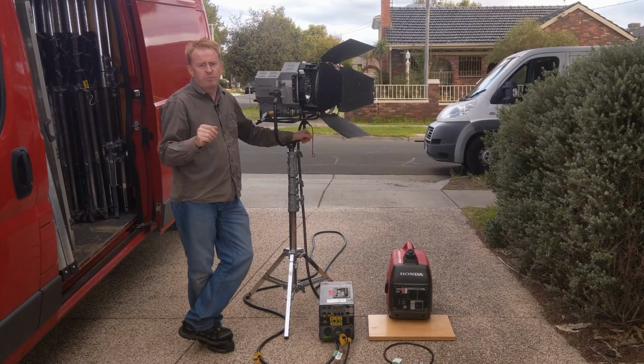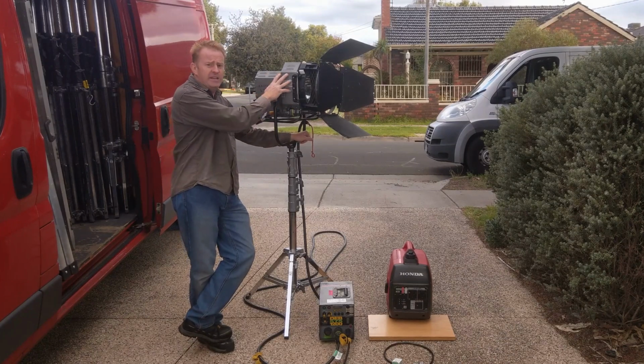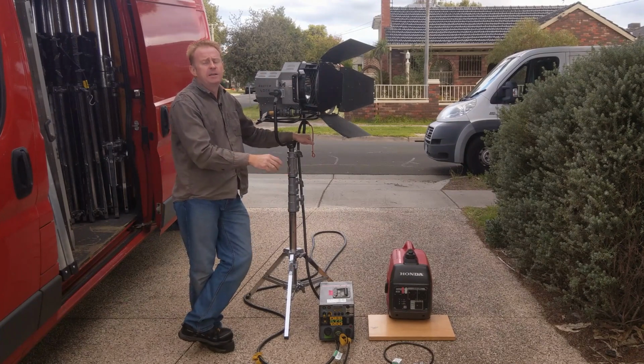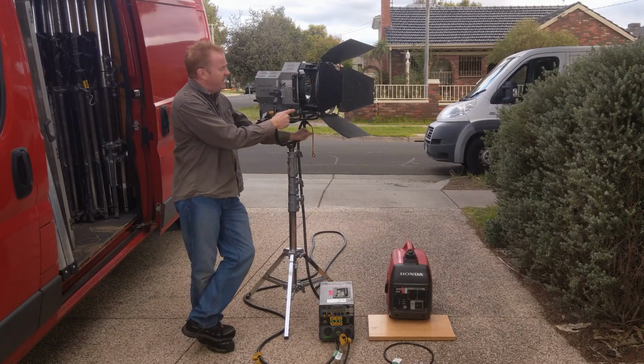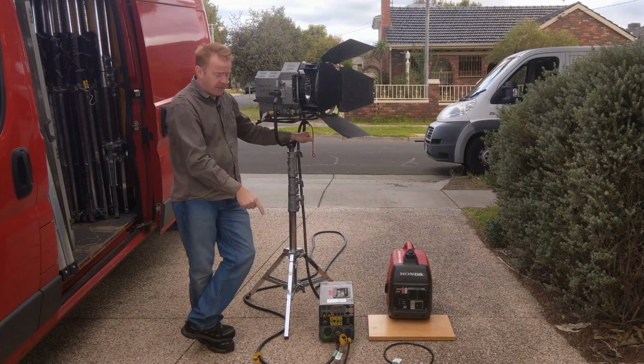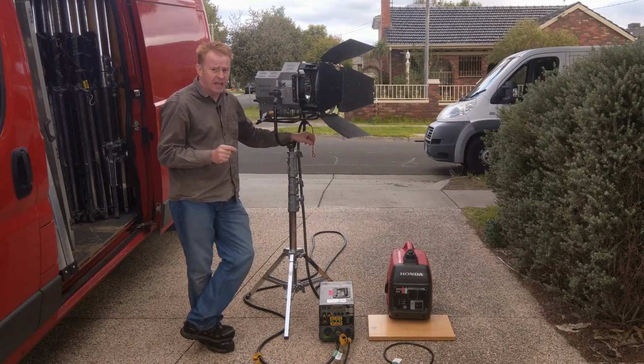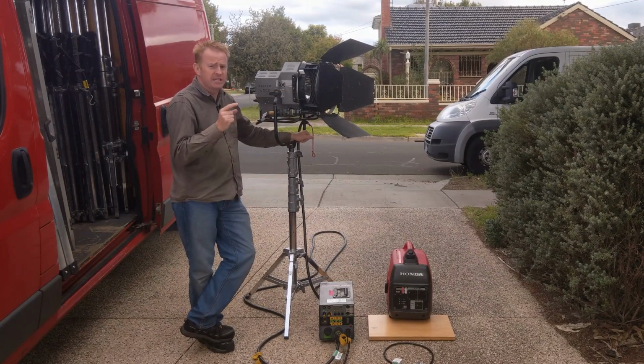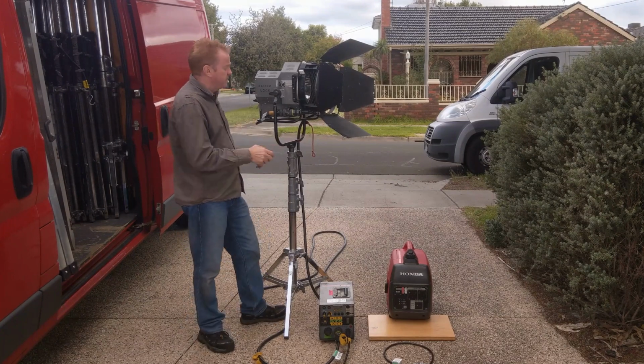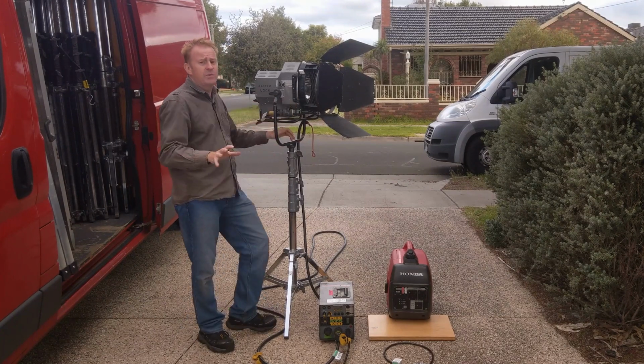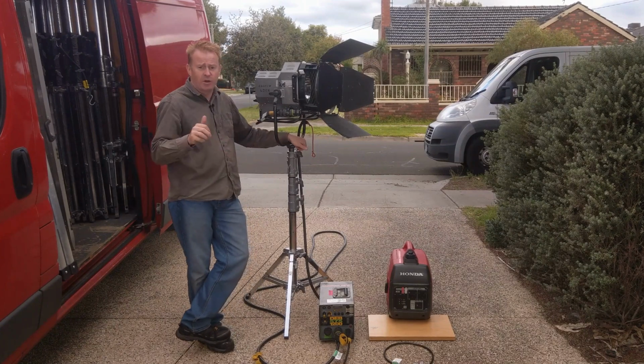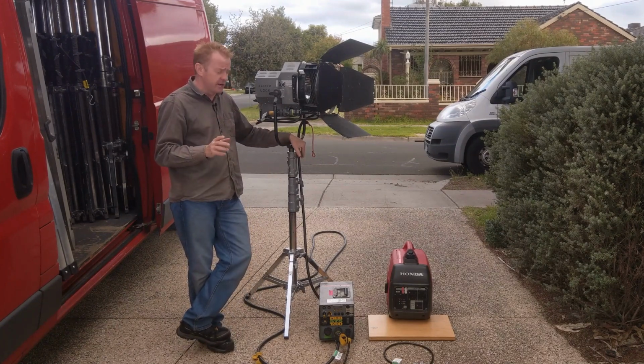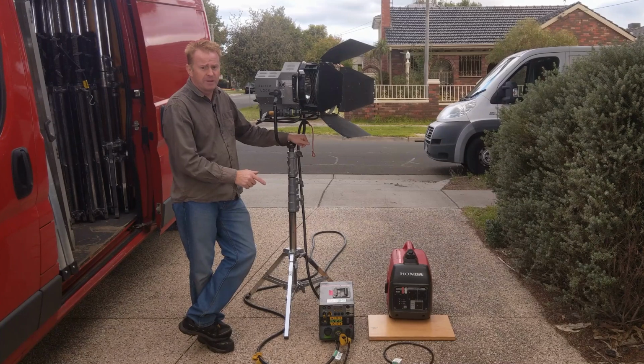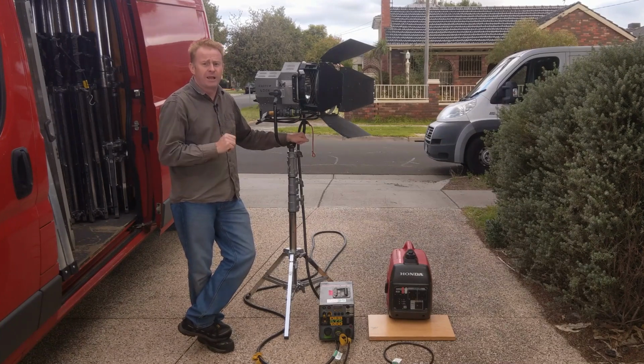So something that is worth pointing out is when you're wiring up a HMI, you should always start at the head and then work your way back to the power. So what I mean by that is you plug the head lead into the head first, then plug the head lead into the ballast, and then the last thing you do is plug the ballast into power. That way you don't get any surprises if you're working up here and you accidentally left the ballast in the on position. Now the next thing I'm going to do is make sure that everything on the ballast is in the off position before I plug it into the generator.